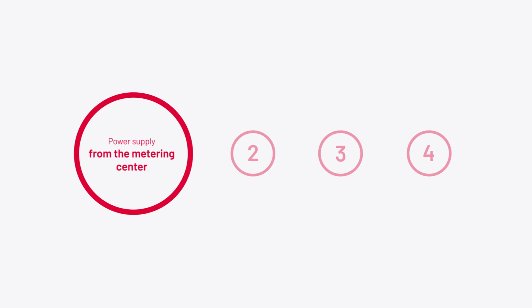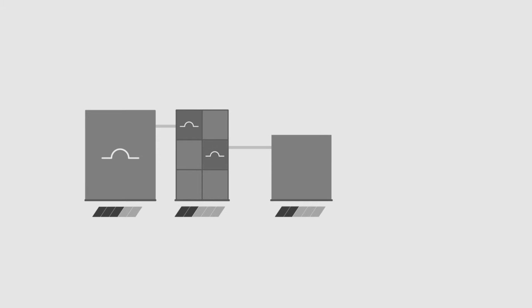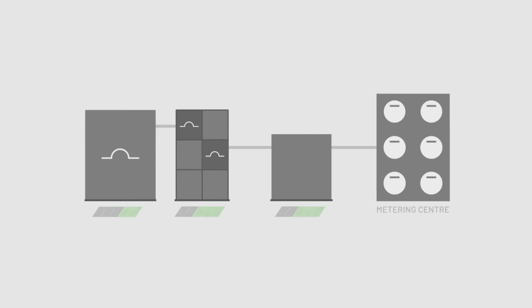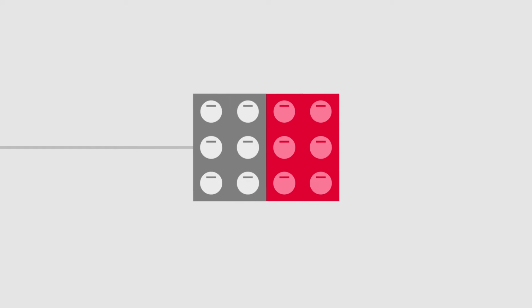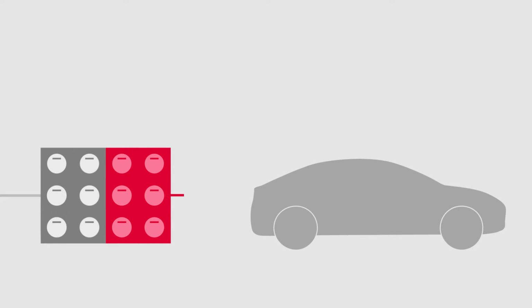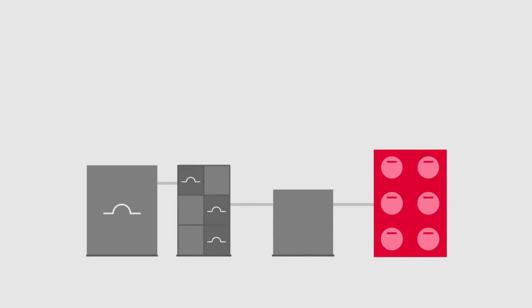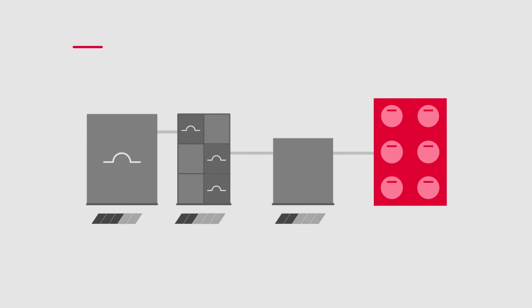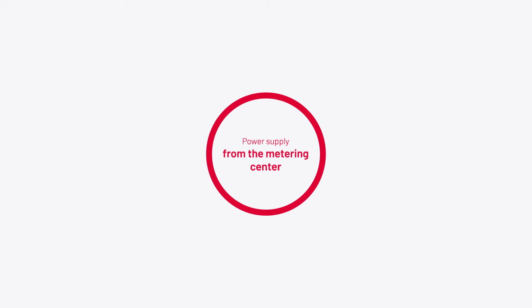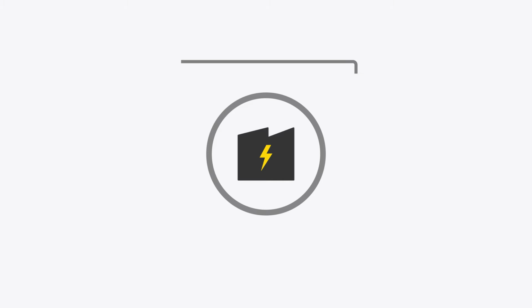Power supply from the metering center. When the unused electrical capacity of the main switch, main housing, and a transformer of a metering center is sufficient, a second meter can be added for units whose main meter is inaccessible. With these new meters, which will exclusively serve to recharge electric vehicles, it is then possible to run a cable to the desired parking space and supply power to the charging station. Adding a column allows for the installation of 6 additional electricity meters. The total number of meters that can be added depends on 2 factors: the unused capacity of the electrical infrastructure and the physical space available. Please note that this solution is only permitted by certain electricity distributors and only when the main electricity meter of a unit is not accessible from the parking spaces.